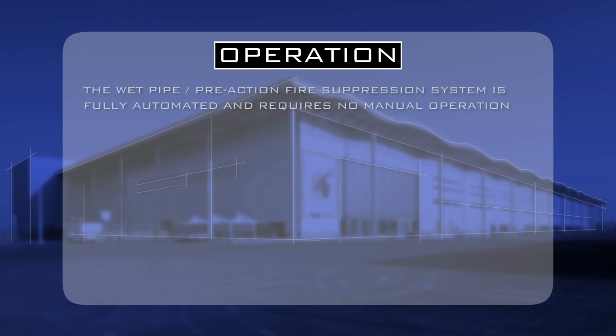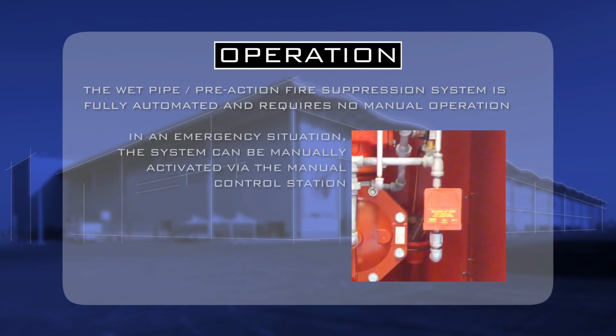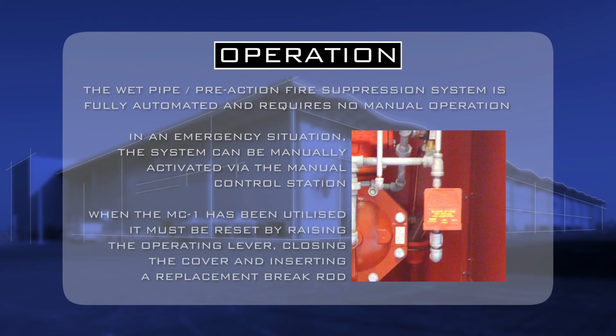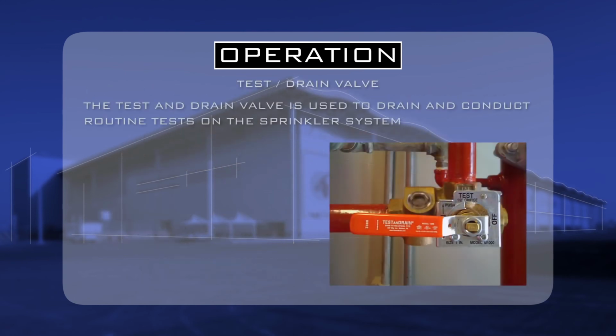The wet pipe pre-action fire suppression system is fully automated and requires no manual operation. In an emergency situation, the system can be manually activated via the manual control station. When the MC1 has been used, it must be reset by raising the operating lever, closing the cover, and inserting a replacement break rod.